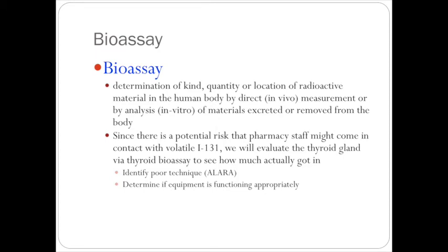So basically, the other thing that this does is it tells us if the equipment is functioning appropriately. Obviously, we test the equipment once a week, but what happens if it broke on day number 2? Then you're going to go 5 or 6 days before you actually identify if the equipment is leaking radioactive iodine. So by doing bioassay at routine levels, we will see if there's a trend where our staff is starting to get more and more iodine in their thyroid gland.